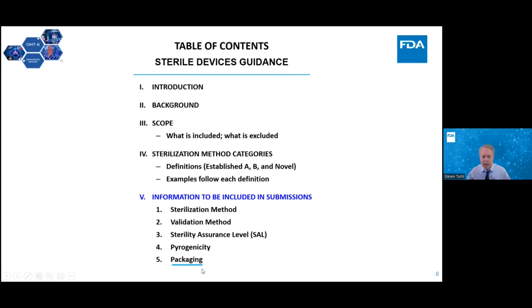So what we typically want to see documented is sterilization method and description of it. That's 1. 2 is the validation method. So for example, maybe the half cycle method for ethylene oxide sterilization. Sterility assurance level, pyrogenicity claim, and lastly, what we're going to talk about is a description of the packaging. That's the sterile barrier system and how it maintains the device's sterility, and a description of the package test methods, but not the package test data itself.